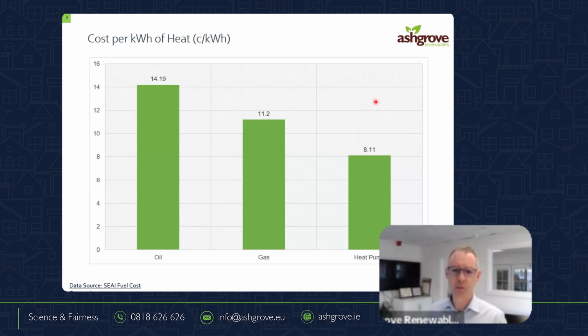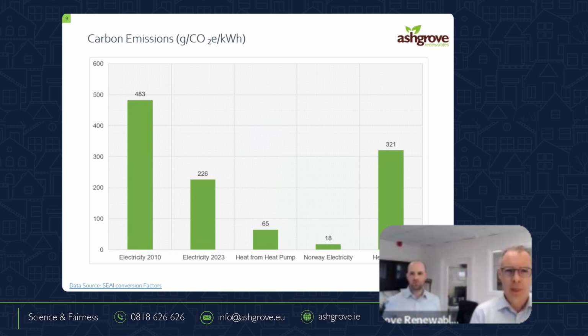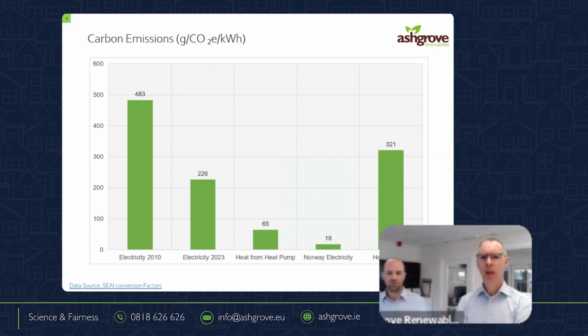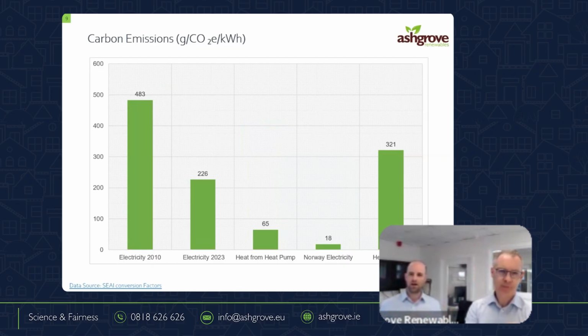28 is a struggle. But it could be, we sometimes see bills ultimately over the year being 3 times what it should be. Now, that's down to I'm using more energy, the COP is lower, etc., etc. But we do see bills that are literally 3 times higher than they should be, in extreme cases 4 times higher than they should be, but we do see them, and it's in no way shocking. It might be shocking to some of you that something could go so badly wrong. Well, and it's what a lot of people are probably hearing is the heat pumps are expensive to run, and they are, and as Shane said, there's 2 main reasons for that. Number 1, they're not designed correctly, so the COP is poorly, and then number 2, people are using a lot more energy just because they're told to leave the system run all day long, and not touch it. So we'll be going through that in a little bit more detail later on.